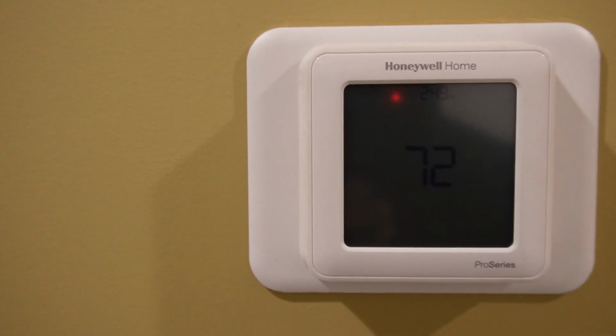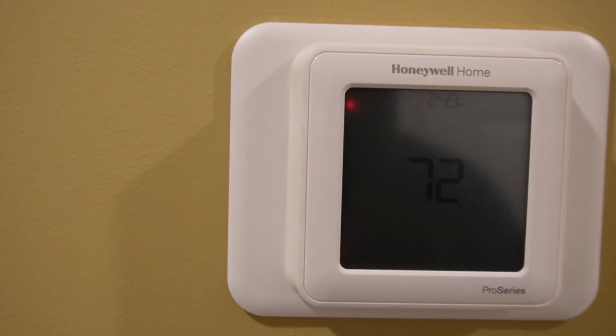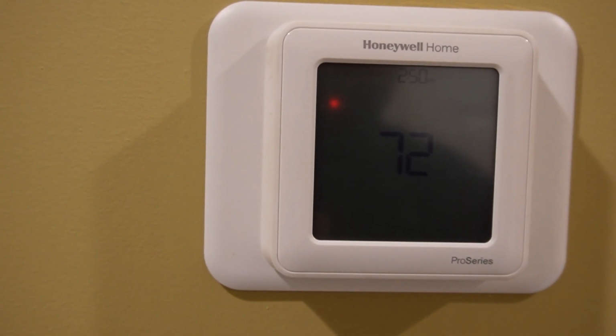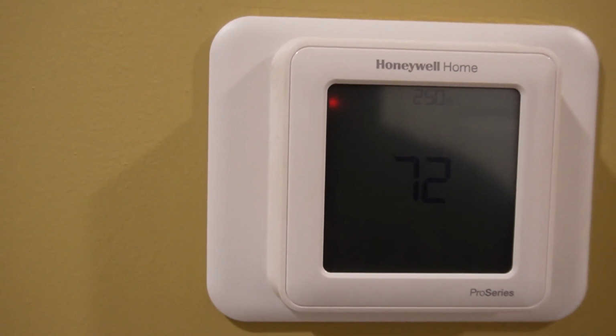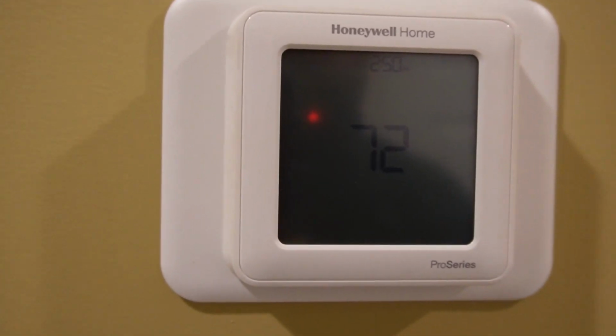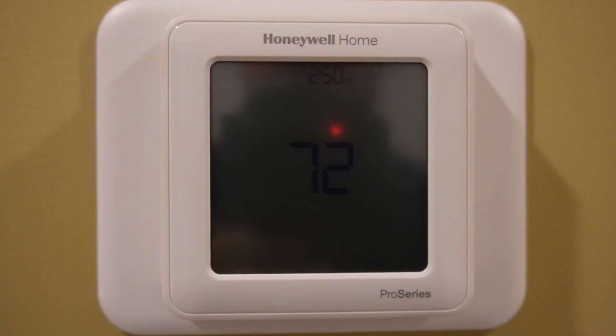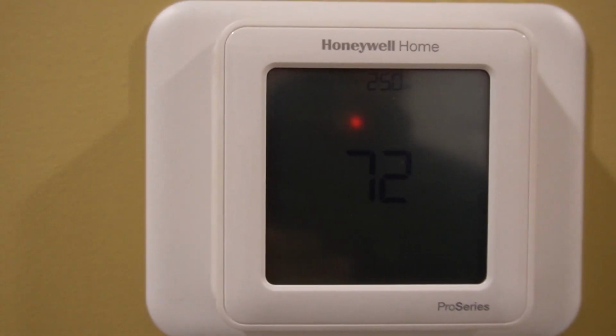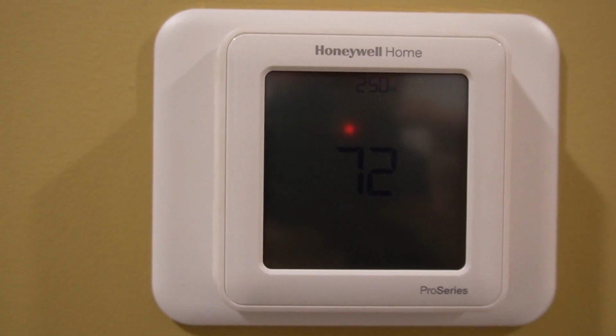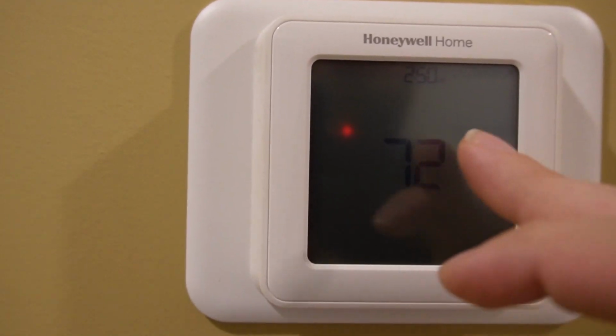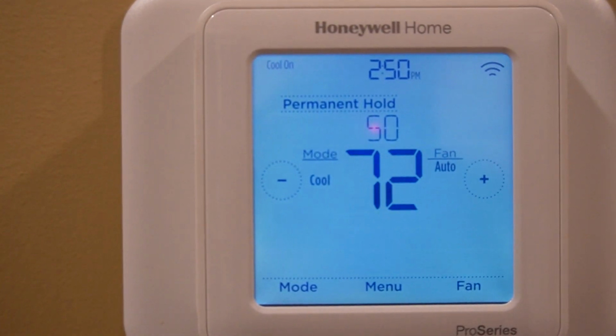Okay, so we are operating with this thermostat here. Just to clarify, the unit in the crawl, the air handler, is communicating with this in your legacy mode - your normal red, white, yellow. So now those two communicate, but our communication from the inside air handler to the outdoor, that's the comfort bridge - that's the communication that's going on. That's the two wire. So we got everything fired back up, and we'll do a wrap up recap here in just a little bit. But yeah, we're cooling down here already. We had it held out so it would stay on, but we're looking good.